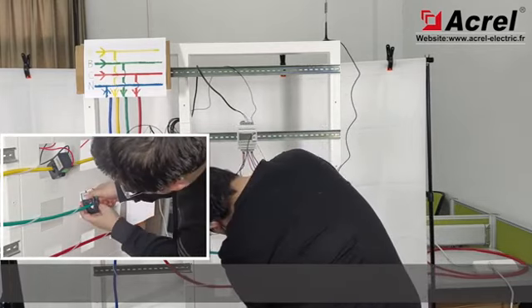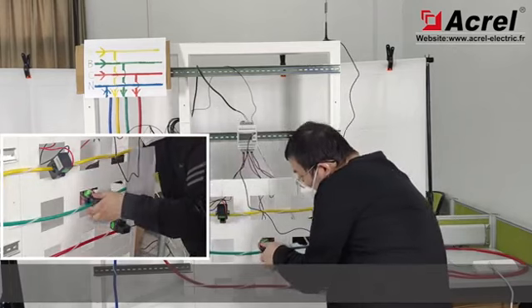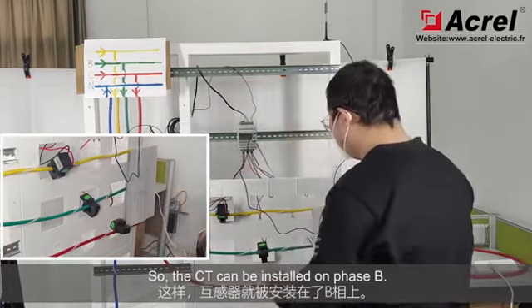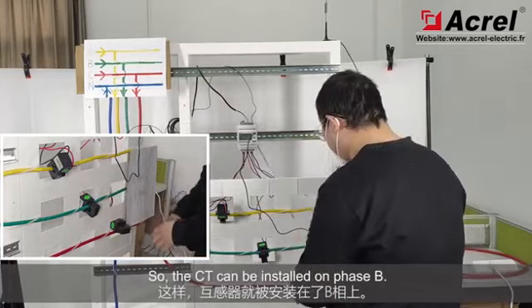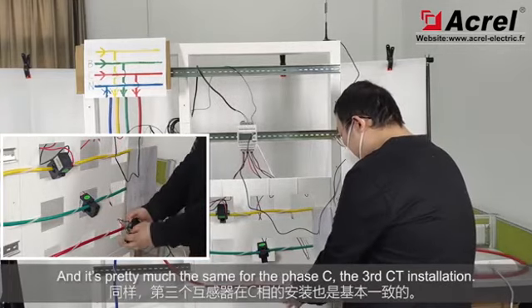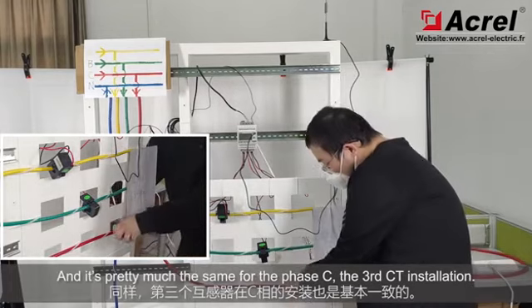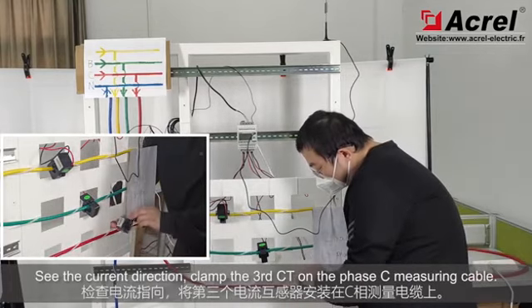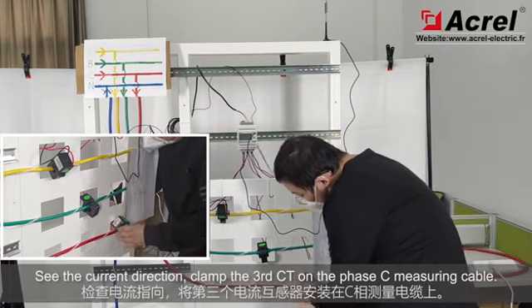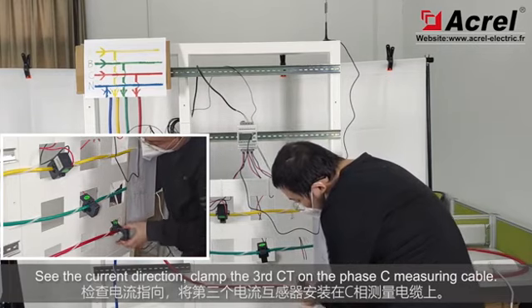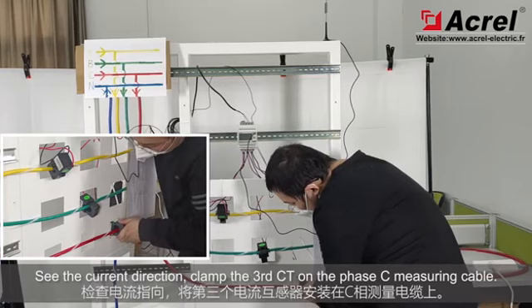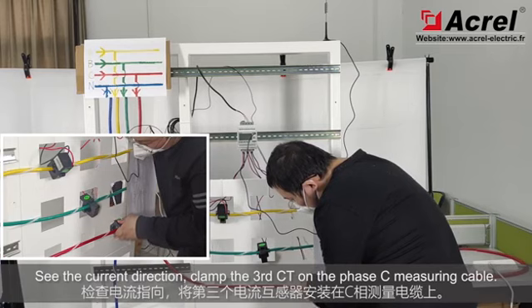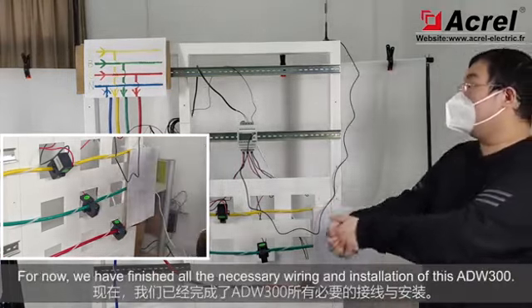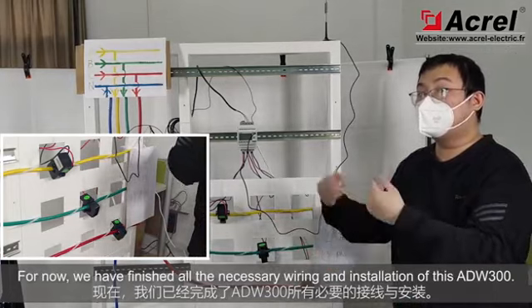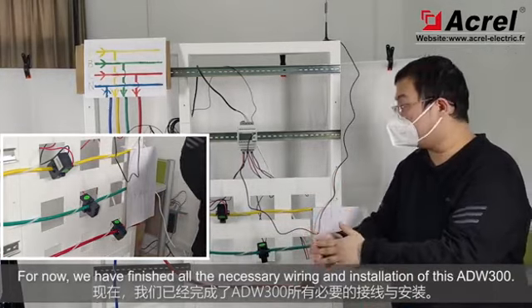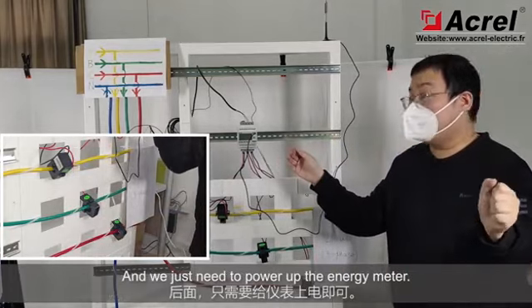Wait a second. Yes, so the CT can be installed on the phase B, and it's pretty much same for the phase C, the third CT. See the current direction, clamp the CT on the phase C measuring cable. For now, we have finished all the wiring, all the installation of this ADW300. We just need to power up the energymeter.